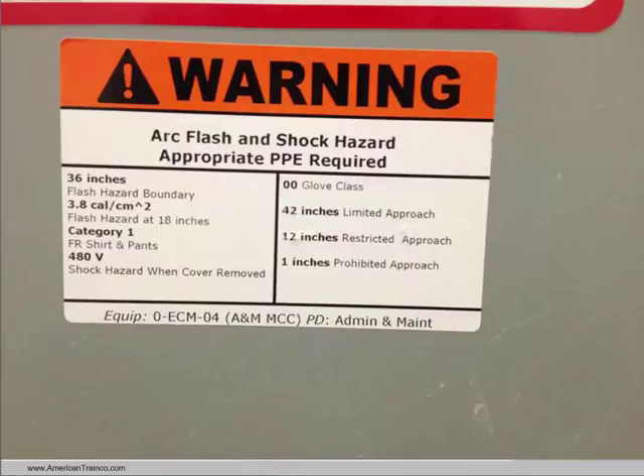So here is the label, and on this label we can see that it does have 3.8 calories per centimeter squared, so that was generated by the analysis. So somebody did an incident energy analysis, and they came up with a number of 3.8 calories per centimeter squared. What we should not see on this label is Category 1. So we should not see the table method in conjunction with the incident analysis. So we have to choose one method or the other. They have spelled it out for us in 2015. Use one method, but not both.